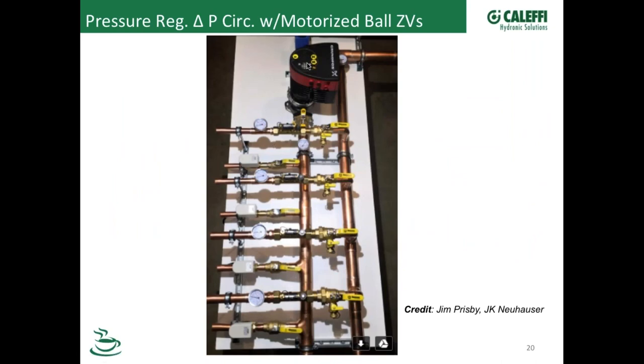But he's running this pump apparently in a fixed speed position, and it's a fairly high head pump. And so he's got about a 45-pound delta P that he's trying to shut off again. So that obviously exceeds our Z1 zone valve. So that's why I chose to use this valve. Number one, he gets that higher shutoff pressure, but also he's got a full flow valve there, that high CV valve. So if these are going out to, again, the snowmelt zones or something like that where he needs a lot of flow, he's got a nice full port valve, as well as that high shutoff pressure.